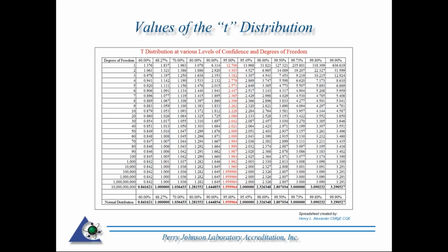So, for example, you can see we've got one sample set. At a 95% confidence interval just based on one, we're going to have to use a coverage factor of 12.7 approximately. You see, as we get closer to 20 and move on down, we're pretty consistent. We're not fluctuating much around a K equals two as our 95% confidence interval. So that's where your K factor comes from, from the student T table and your confidence interval based on what you're stating. Like I said, most folks in calibration, sometimes we see them at 99%. But more often than not, 95%, which is highlighted there in the red.